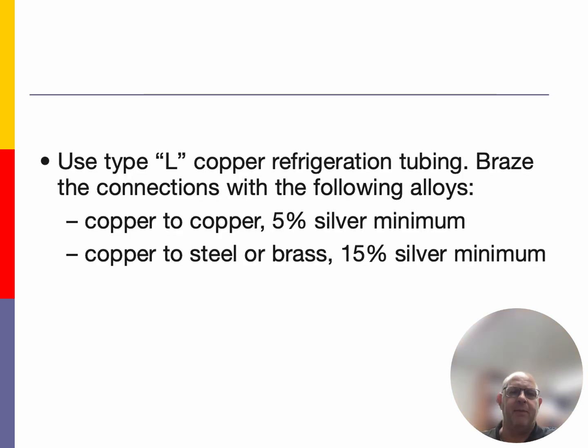Braze the connection with a minimum 5% silver braze. Nothing less than that. So whenever you're brazing, make sure you're using 5% minimum. There are some really cheap brazes out there, but make sure you're using the correct brazing. Look at the cover of the braze, and it will tell you the silver quantity that's in that particular tube. When you're doing steel to brass, you want a higher silver content. 15% minimum on that.